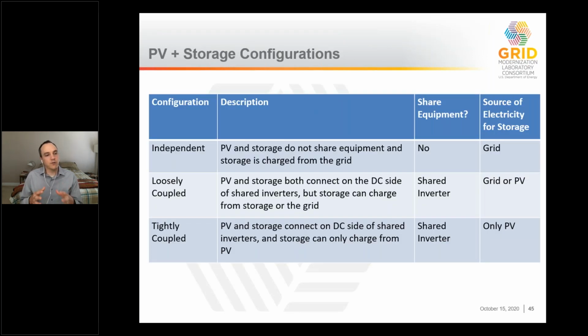If you had a solar and storage system you wanted to combine, there are different configuration options. We start by having them completely independent: a PV plant and a storage plant sharing no equipment, no shared infrastructure, no point of interconnection limit constraining output, and the storage asset can charge and discharge from the grid as needed. That's our baseline configuration.